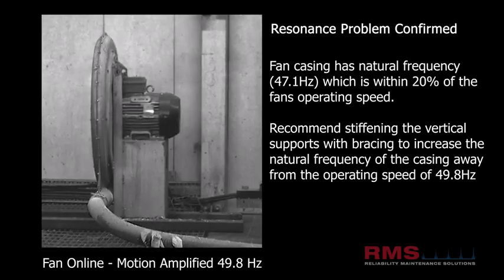So what I'm recommending on this is stiffening the vertical supports, maybe some bracing to reduce the vibration levels by increasing the natural frequency of the structure from 47 to above the rotational speed.